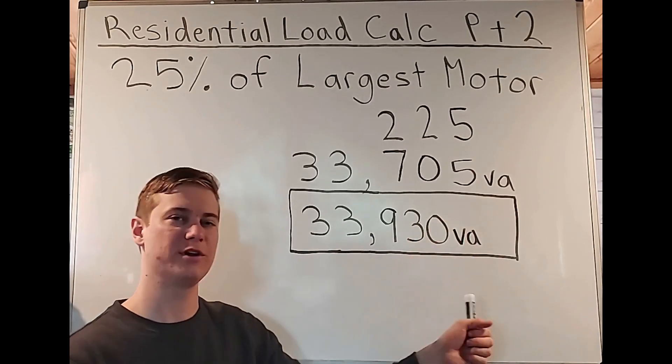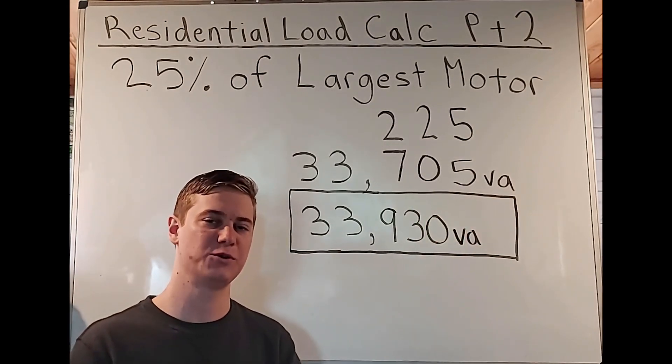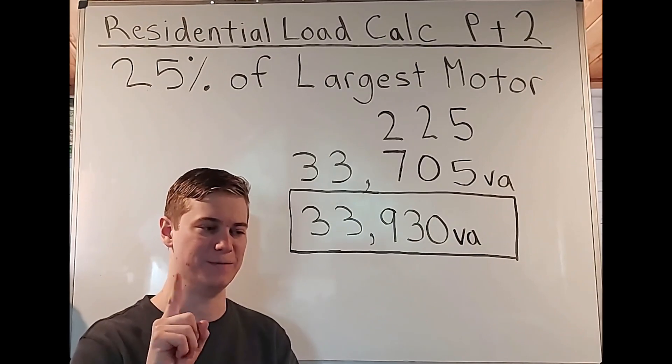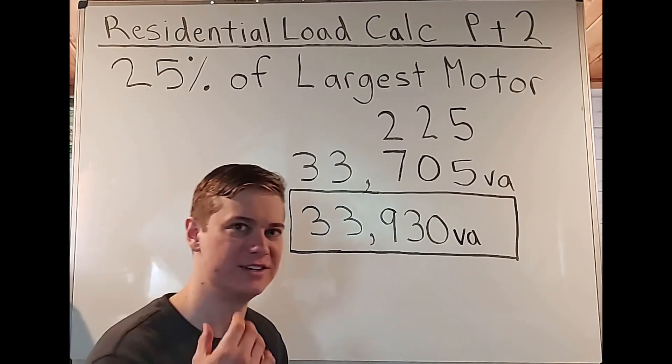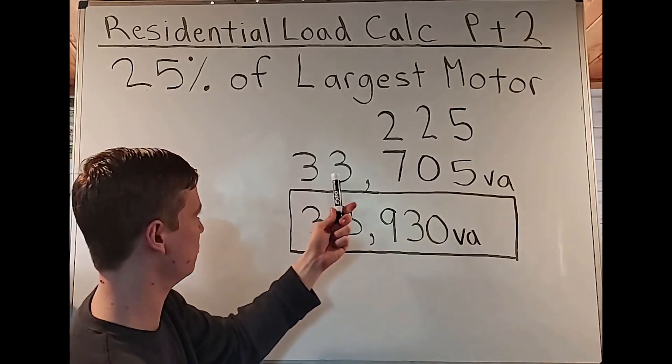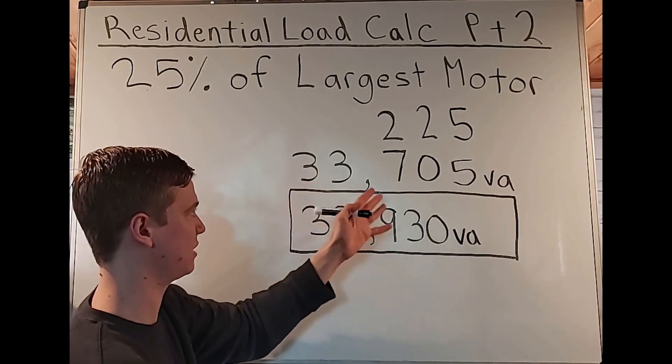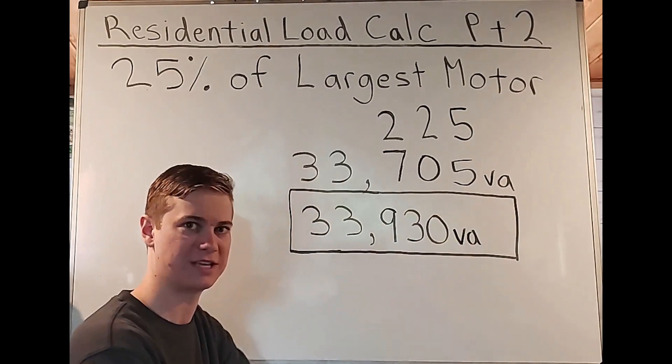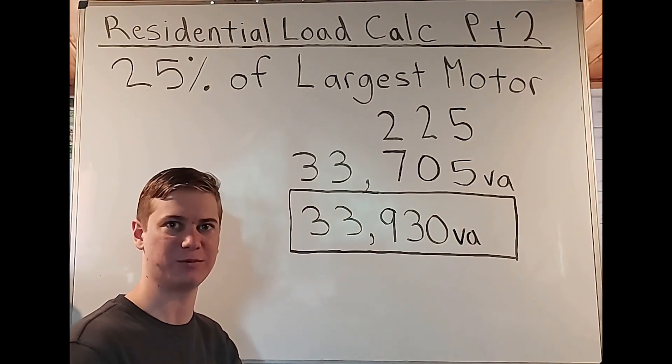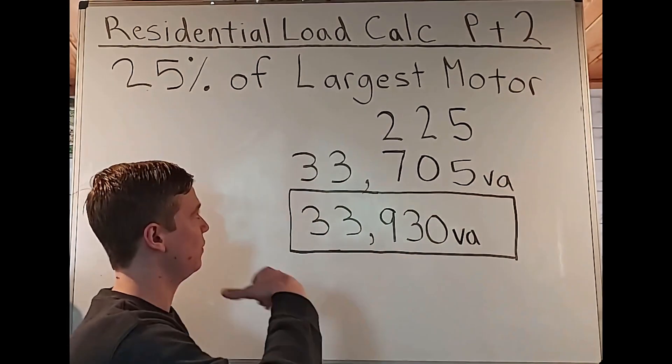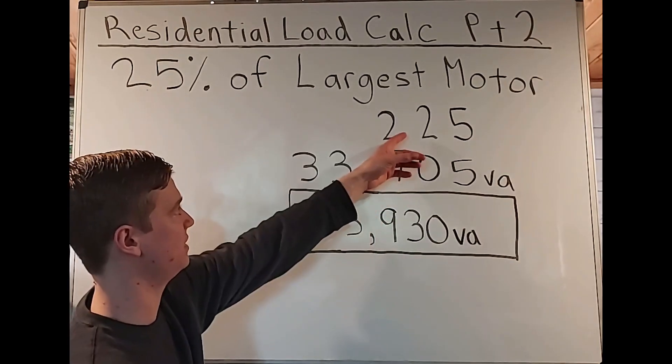So now this is kind of weird, because no matter how many units you have, you're only going to add this one time. So this means if I had a duplex, we had two units on the same feeder, and we came up with this answer 33,705 volt amps, and the same thing, it had a disposal that was the 900 volt amps, we multiplied the 25% and we ended up with 225.